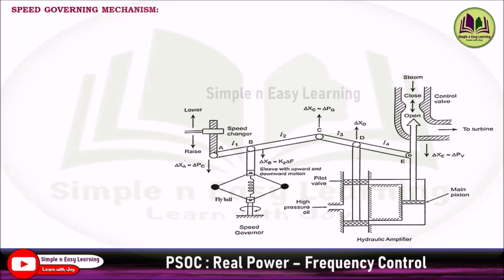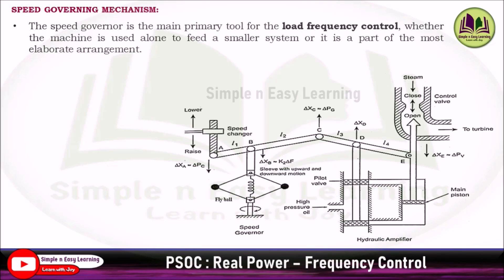This is a complete structure of the speed governing mechanism. The speed governor is the main primary tool for load frequency control, whether the machine is used alone to feed a smaller system or it is part of a more elaborate arrangement. As the load varies, the speed changes, and since speed is directly proportional to frequency, the frequency gets affected. This load frequency control is much needed in power system operation and control.